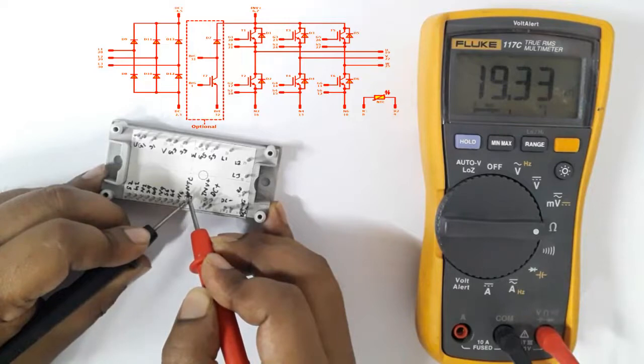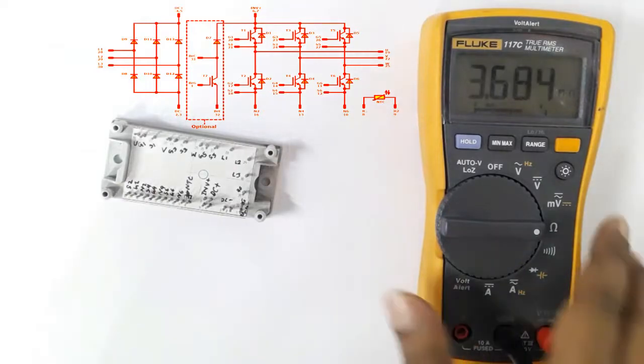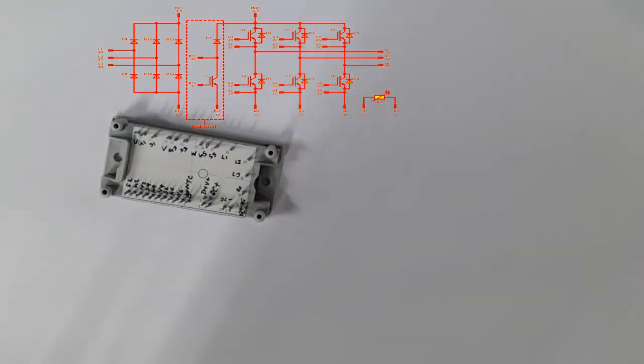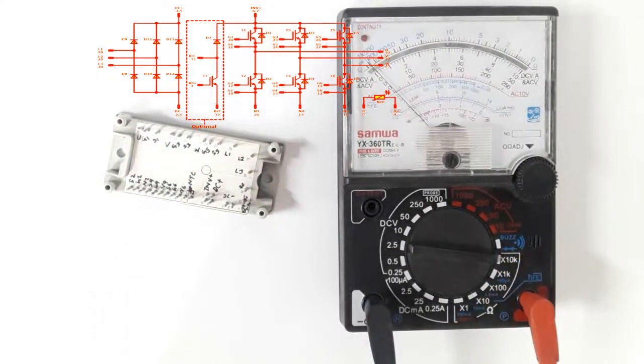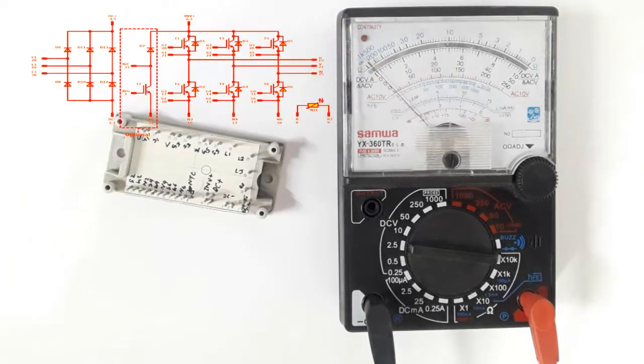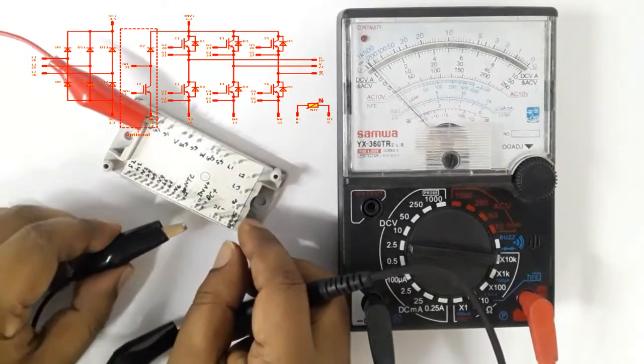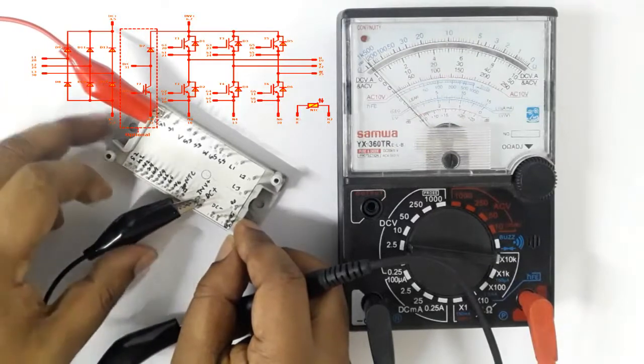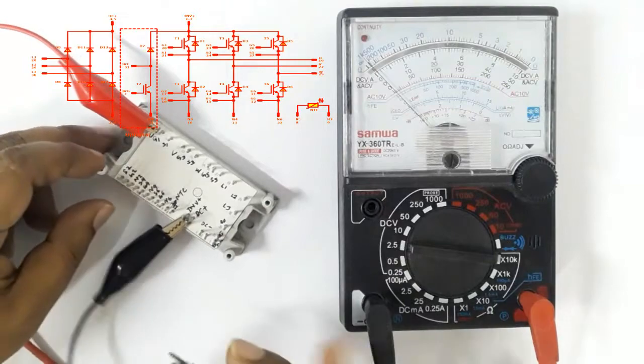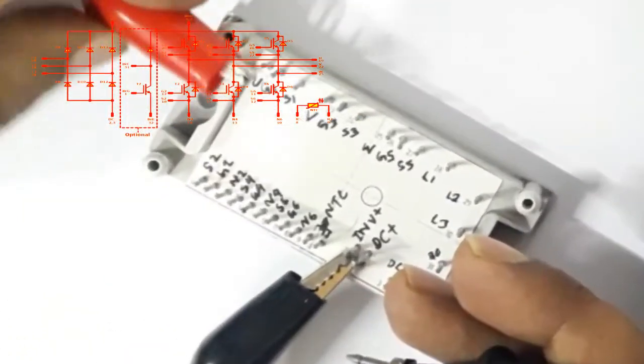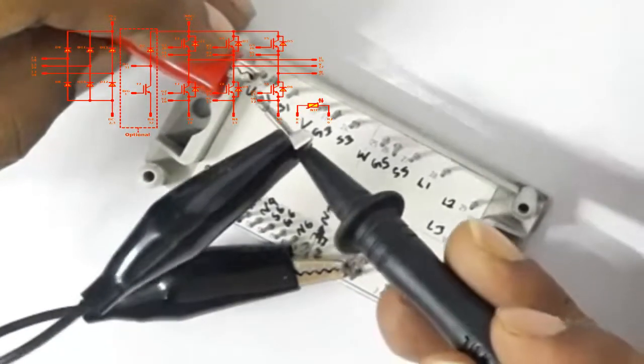Now we want to test IGBT gate. We want to test IGBT gate for U terminal first. Set black probe in IGBT inverter positive terminal and touch red probe on U, and now testing gate G1.